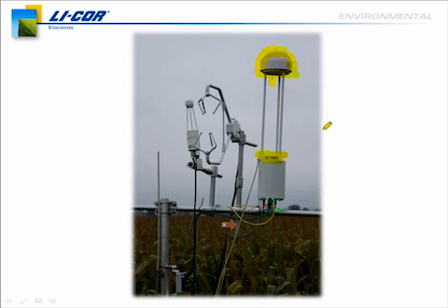Now, the instrument also has Ethernet output, so you can send data directly out from the instrument to either a data logging device or to a network, so you can access the instrument remotely. If you have a networked site, you can just sit at your desk, pull up the instrument, and make sure it's operating properly. You can also collect data over the network, either directly from the instrument itself, or if you're using our logging device, you can connect and pull data files across from that logger.